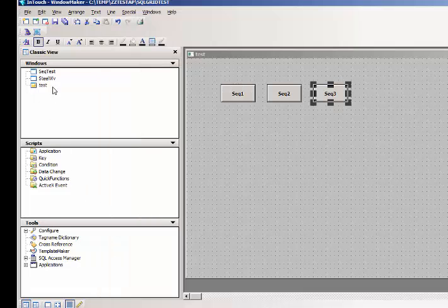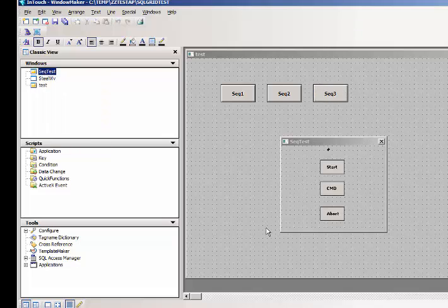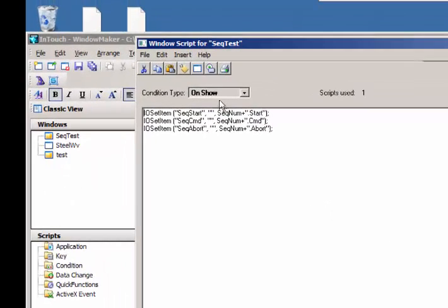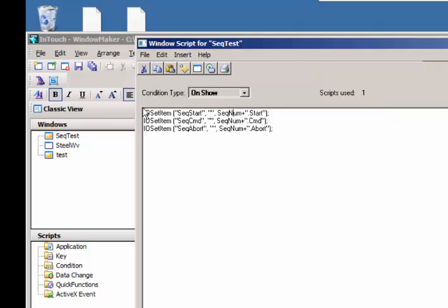So if I look at the actual pop-up itself, sequence test, if I open him up and I go look at the window scripts, this is where the work is being done. On show, when this window first pops up, this is where I'm going to set the sequence number. Remember I'm passing in that sequence number from the button, whether it's going to be sequence number 1, 2, or 3, and it's going to set the address, the IO address of these different tags.